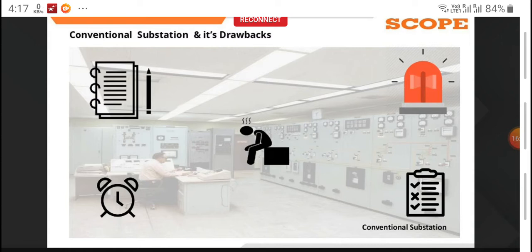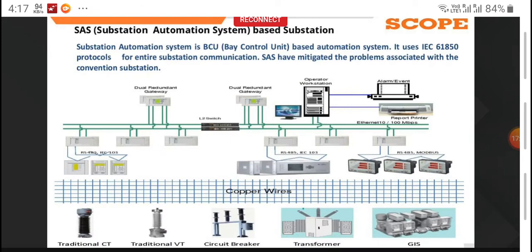Even when it goes to the primary equipment, there is not much automation. But when it comes to controlling the switchgears, transformers or breakers, or parameterizing, or putting in the energy values, we have done some automation in this area. That's what we are using right now, the substation automation system. Mostly 99% of our substations are SAS substations of this type, where you have conventional CT and conventional PT, which give 1 ampere secondary current output, or 110 volts secondary voltage output, and the breakers having tripping coils or closing coils, and transformers, and some GIS system.